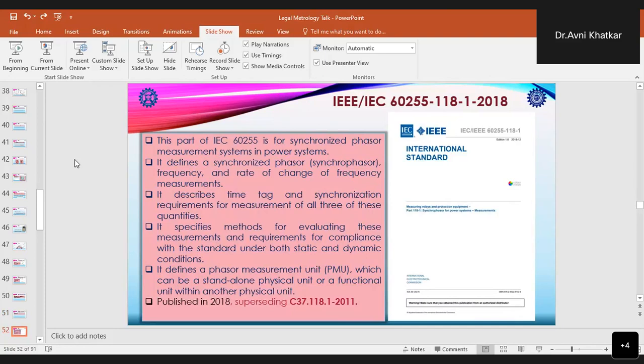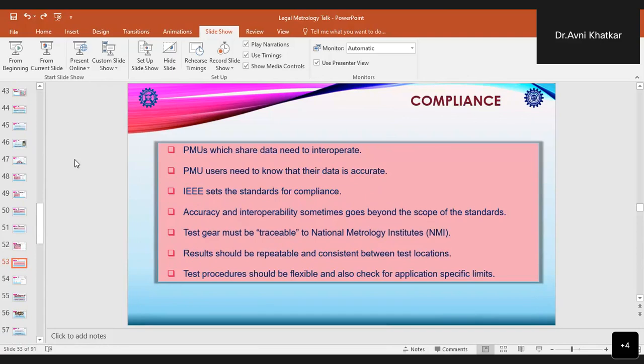This international standard defines a synchronized phasor, that is synchrophasor, and the frequency and rate of change of frequency measurements. It also describes the time tag and synchronization requirements for measurement of all three of these quantities, and it specifies the methods which are required for evaluating these measurements and requirements for the compliance with the standard under both static and dynamic conditions. And it defines a phasor measurement unit, that is PMU, which can be a standalone physical unit or a functional unit within another physical unit.